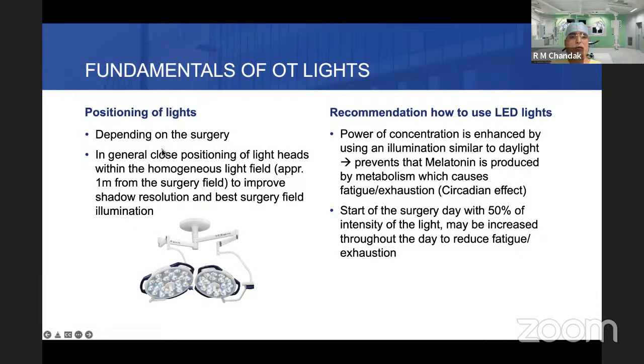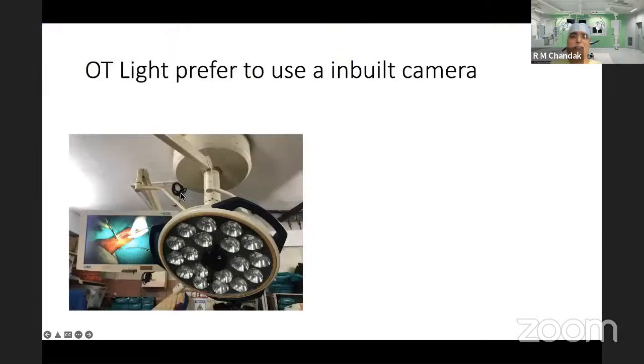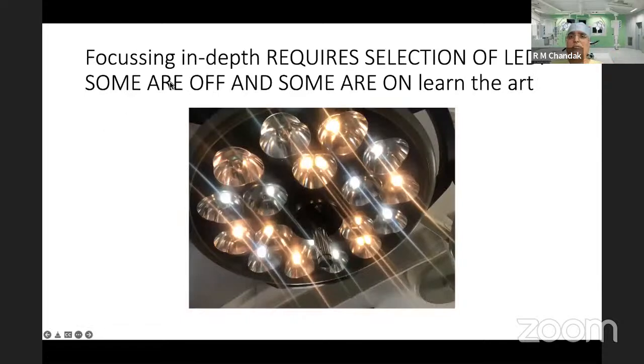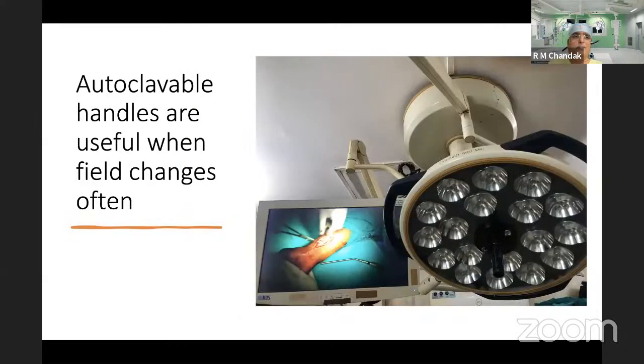It depends on the surgery. Close positioning with the homogeneous light field, approximately 1 meter from the surgical field, is the best. For an OT light, prefer to use an inbuilt camera so that you can have a proper surgical recording, and then somebody else is not required to come into the OT field. Focusing in depth requires selection of LEDs. Look at this light dome. So this is depth focusing. In this, there are certain LEDs which are off, and there are certain on, and that gives a parallel light beam into the depth, and that gives a good field.